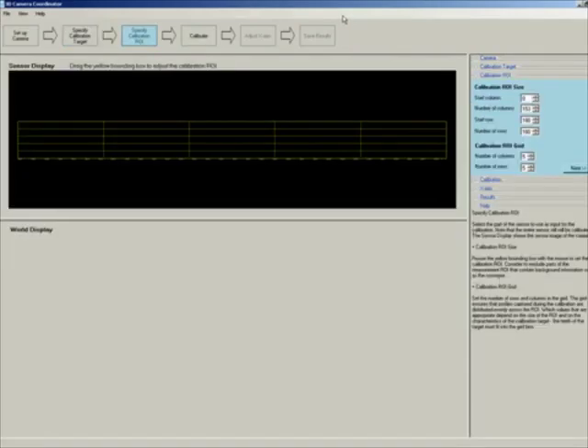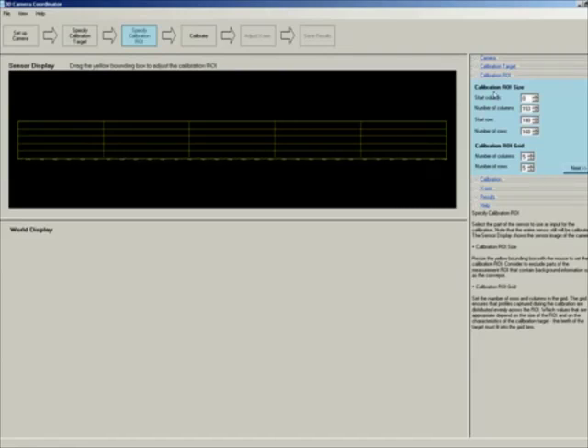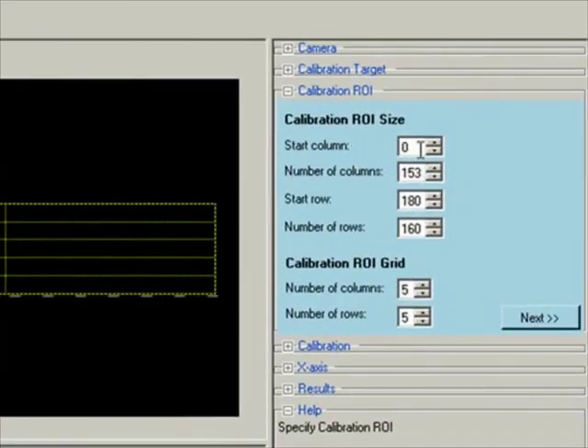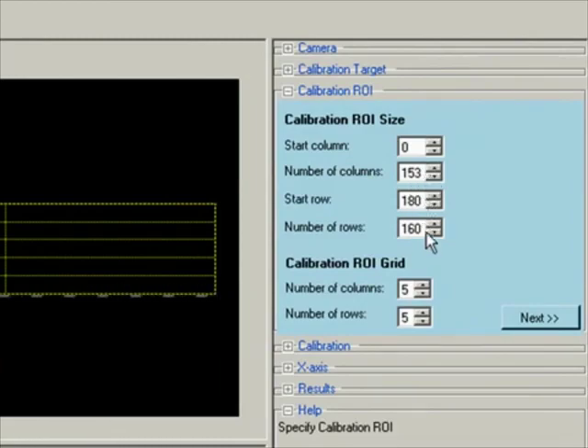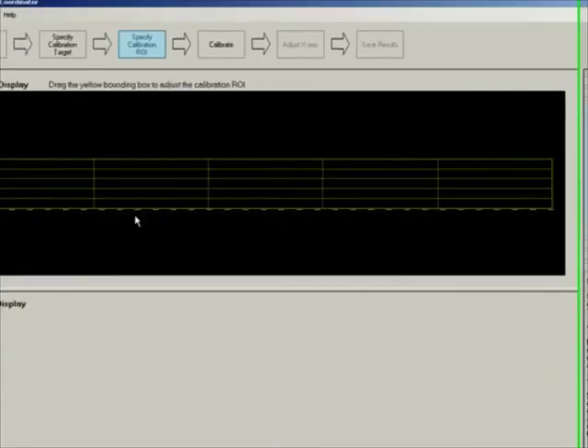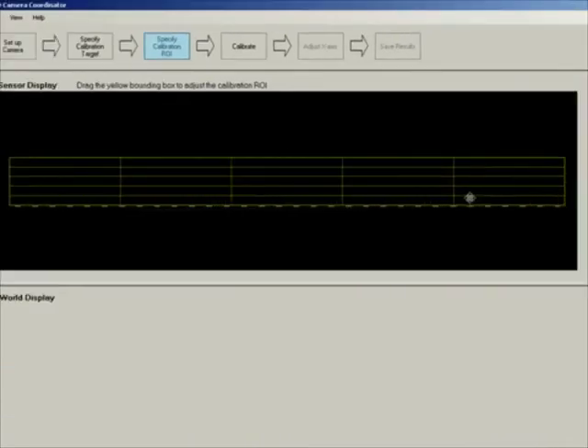The calibration ROI is the area you are interested in calibrating. By default, the calibration ROI is extracted from the parameter file you specified. In my parameter file, the start column was 0 using all 153 columns, the start row was 180, and the number of rows was 160 — and that is what is being shown highlighted in yellow.